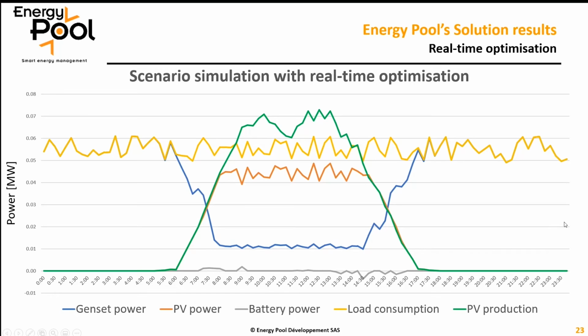During nighttime, we have no PV production, so the load is 100% covered by the genset. At around 6, PV starts to produce, so we progressively reduce the share of the genset and increase the share of PV. Around 8 a.m., the PV production is more important than 80% of the load, so we have to curtail PV production to respect the 20% of the load that should be covered by the genset. Jean-Pierre, if you pick one time, we will see.